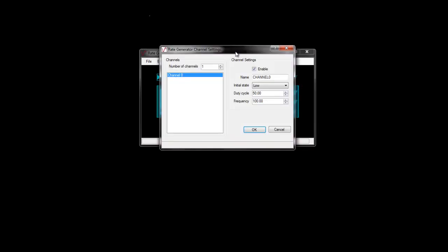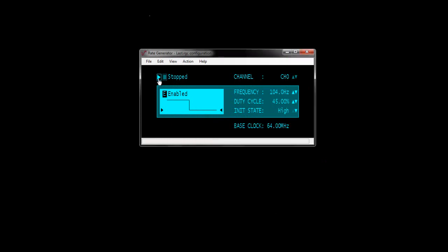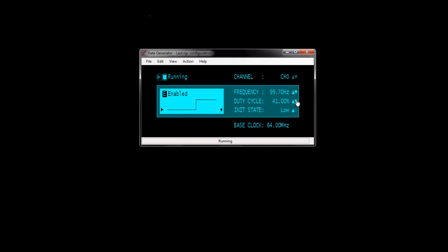Select Edit > Channel Settings to display the rate generator channel settings dialog box. You can set the initial state of the waveform to high or low, the frequency of the waveform, and the duty cycle of the waveform. Click OK to save these settings. Now click Start to output the waveform to the selected counter timer output channel. You can also change the initial state, frequency, and duty cycle of the waveform while an acquisition is running by clicking these hotspots.